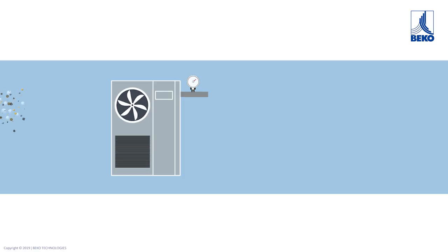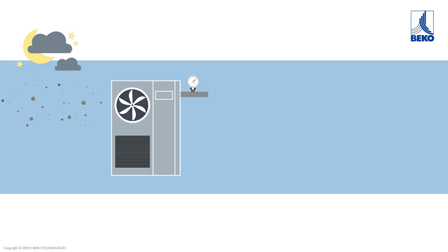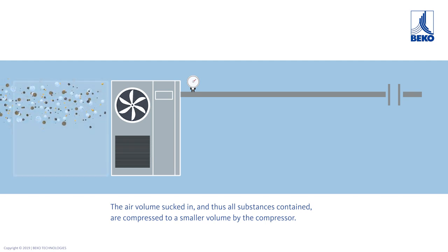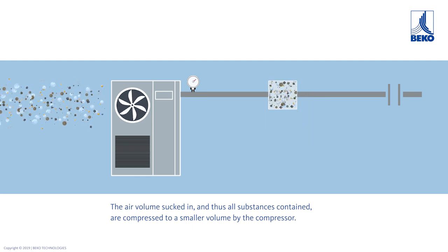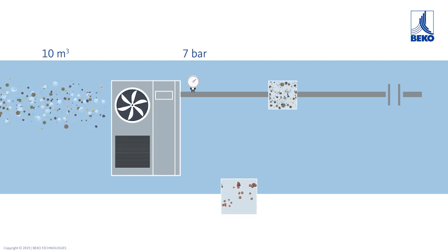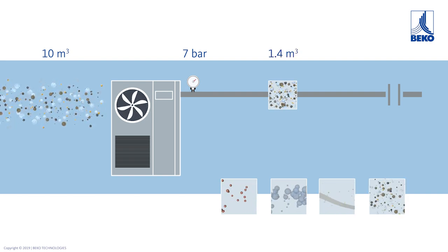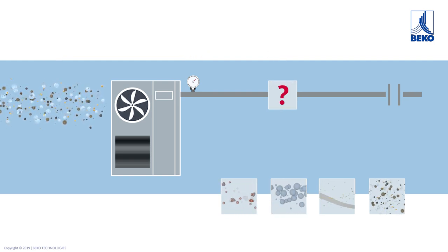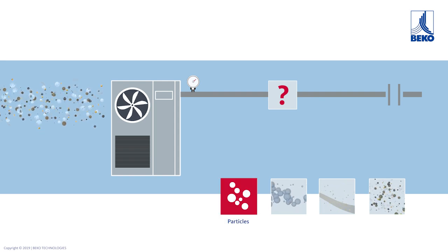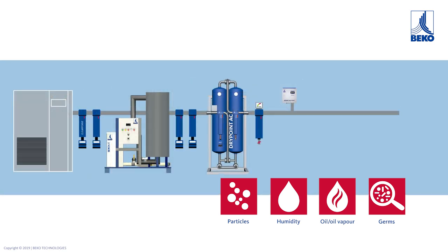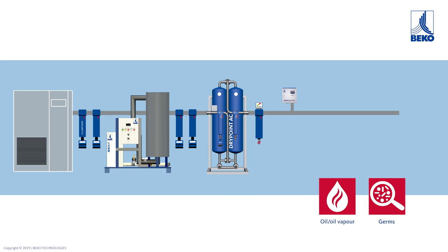It should also be noted that ambient conditions such as day and night can change considerably. The air volume sucked in — and thus all substances contained — are compressed to a smaller volume by the compressor. For example, with a compression of 10 cubic meters of ambient air at a system pressure of 7 bar, after compression all components are contained in approximately 1.4 cubic meters of compressed air. It must therefore be expected that after the compressor, a mixture of particles, humidity, oil vapor, and germs is contained in the compressed air.